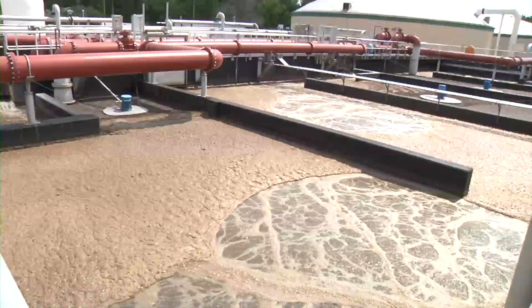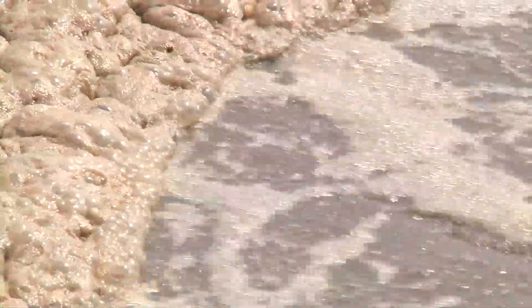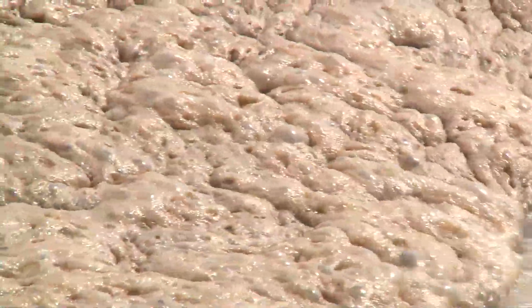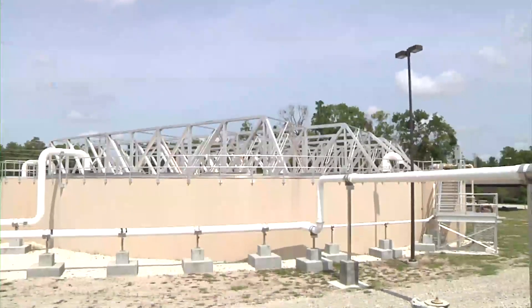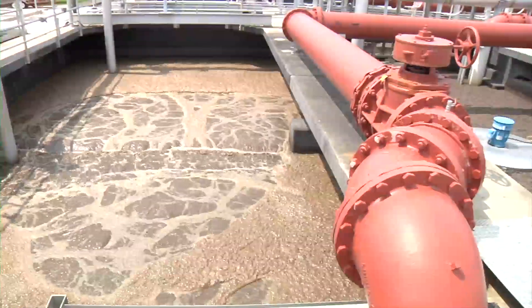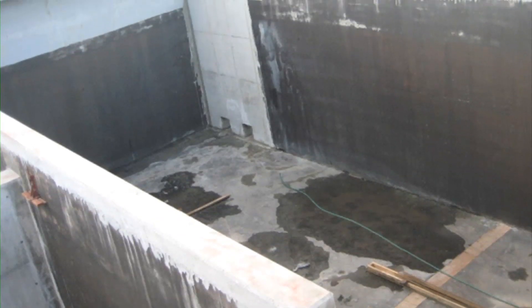Arlington East was an interesting plant that was producing pretty good effluent. Our nitrogen levels, just during normal operations, were somewhere between 9 and 10 milligrams per liter. Our goal was to get below 6. One of the challenges on this plant was to build a primary clarifier. The second challenge was to find a way to convert the MLE process to step feed. We were seeing somewhere between 14 and 15 million gallons a day on a 20-MGD plant — so it was 75 percent loaded — and we were going to have to take basins off while we worked.